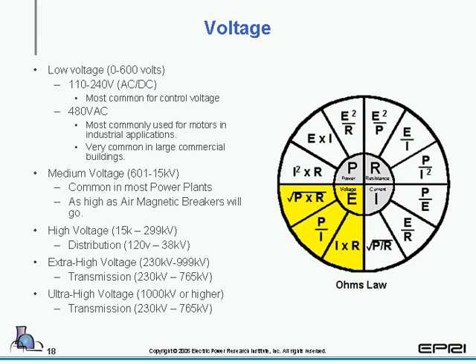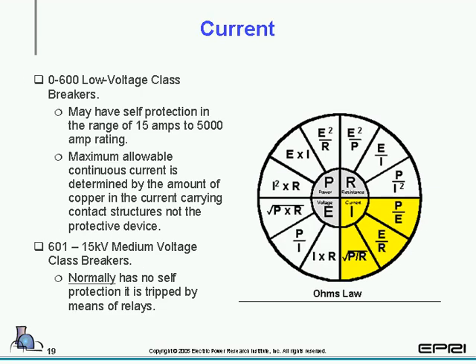The very first one we want to take a look at is the voltage. Normally in the U.S., low voltage breakers are considered between 0 and 600 volts. Medium voltage is 600 volts to 15 kV. And then we continue on with high voltage, extremely high, and ultra high. The basic thing is, the greater the spacing between the phases and the phases to ground, the higher the voltage can be. So a lot of voltages depend upon the insulation.